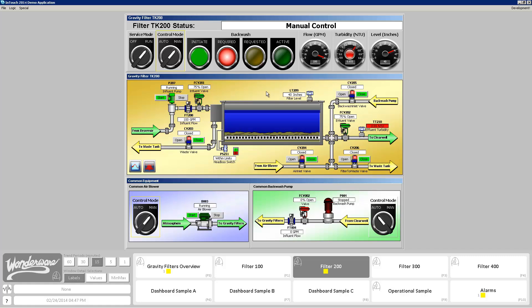Now some of these things require action and some of them don't. With this inconsistent usage of color coding, what can happen is that the operator can be conditioned that red does not require action, when in fact sometimes it does. You can then condition your operators to ignore the backwash required indicator because red just became a normal condition in the system and wasn't automatically triggering a response.